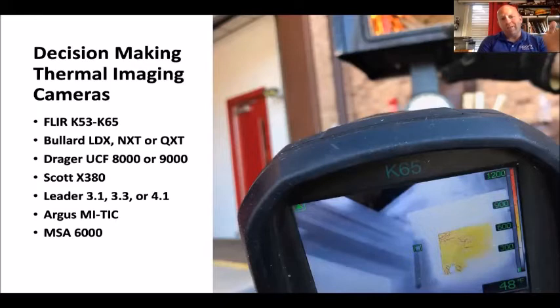Outside those Bullard models, to me the image quality isn't high enough unless you're getting the exchange program where they rip the guts out and put new stuff in. For Drager users, stay within the 8000 or 9000 because you can see much better — the 6000 and 7000 are very low resolution, I classify them as situational awareness cameras. Scott still makes the X380 which hasn't been changed since 2012; it was great when it first came out but isn't anymore. The Leader 3.1, 3.3, or 4.1 is a good decision-making camera at a lower price point. The Argus MI-TIC, whether the E or S, is a good decision-making camera, as is the MSA 6000.